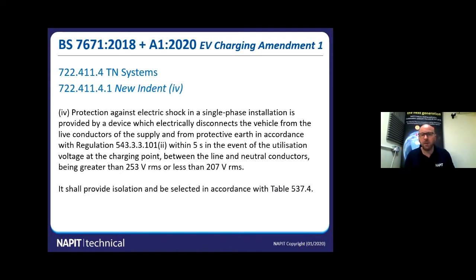It must also provide isolation, so it needs to be selected in accordance with table 537.4. If you look at that table, it gives you all the devices that meet the requirements for isolation. And a lot of these charge points have contactors in there to deal with that isolation, so that's a great solution. If we get any kit, whether it's built into the charge point or an external bit of kit, and it can meet that requirement, then we don't have to worry about the TNCS. We can use TNCS, no problem, because we've got a device that under fault conditions will disconnect the problem.